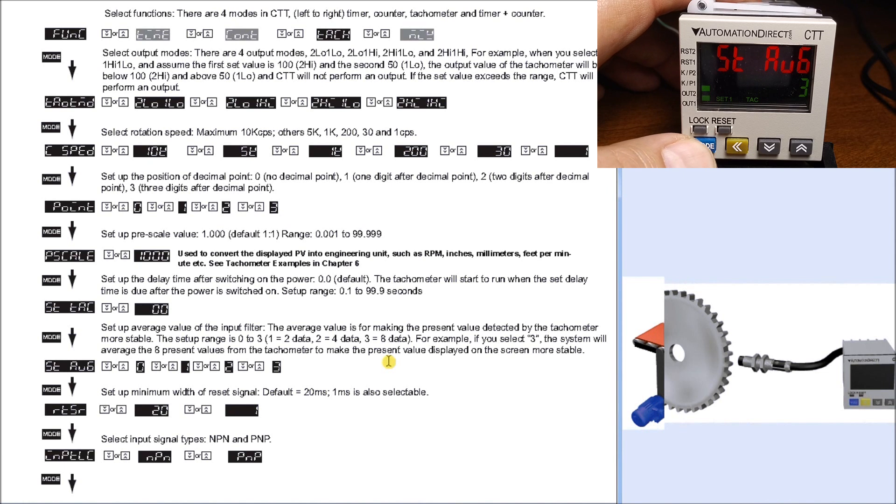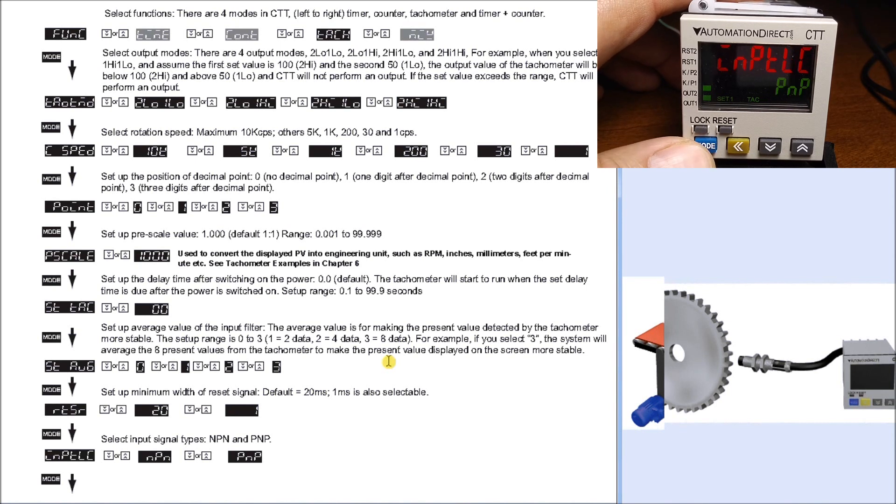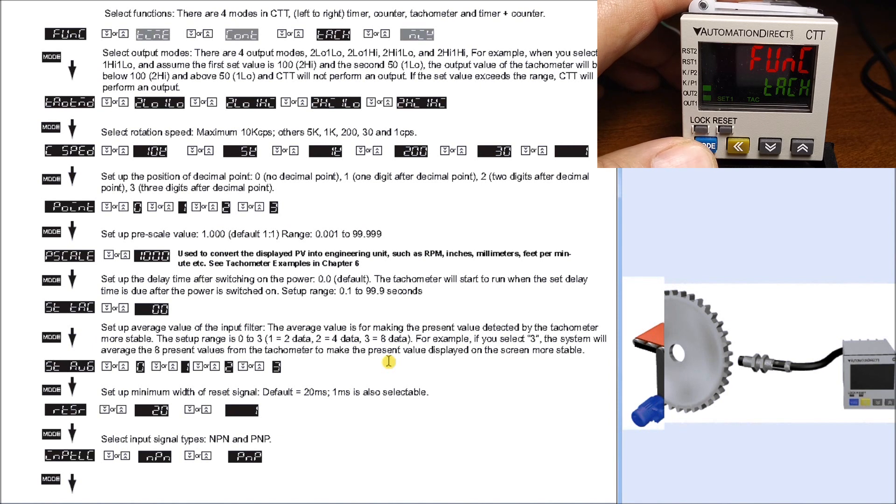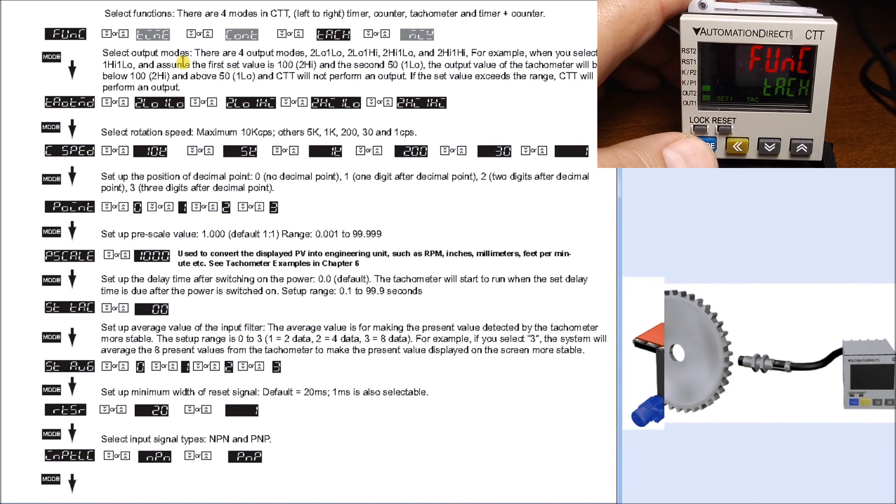Hitting mode again, we have a reset which is set for 20 milliseconds - that's the time it takes for the output to actually reset. Hit mode again and we have our input type, which is set for PNP - this means the way it's wired to the CTT itself. Mode again brings us back to the function. To get out of program mode, we hit and hold mode again for three seconds.